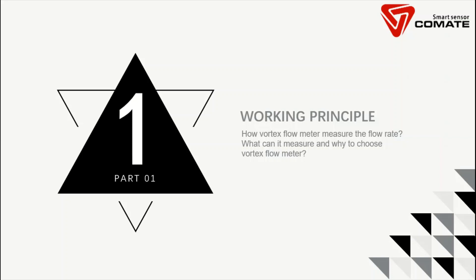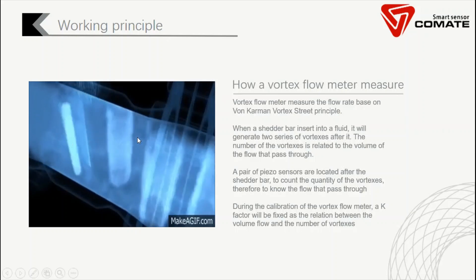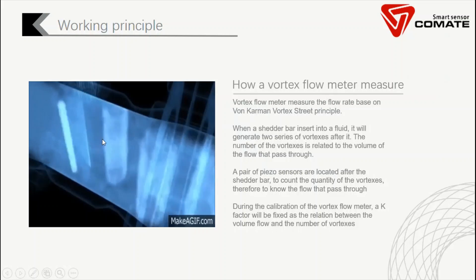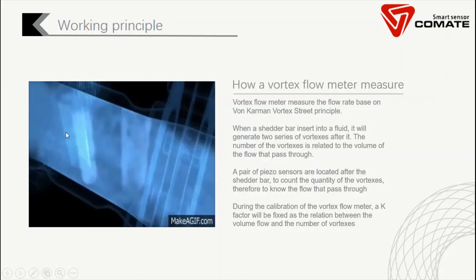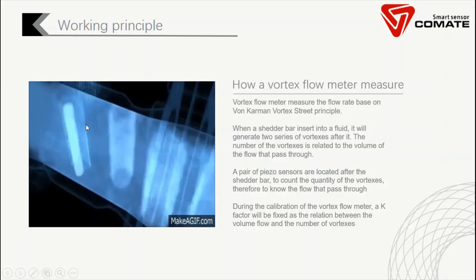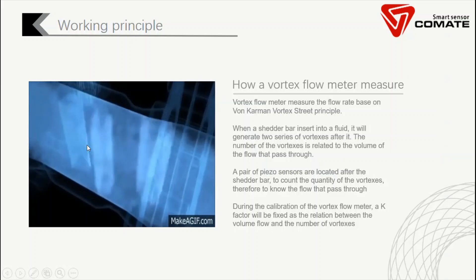Let's begin with the working principle. How can a vortex flow meter measure the flow rate, what can it measure, and why choose a vortex flow meter? A vortex flow meter is designed based on the von Karman vortex street principle. When a shedder bar is inserted into the fluid, it will generate two series of vortexes after it. The number of vortexes is related to the volume of flow that passes through — this is called von Karman vortex streets.